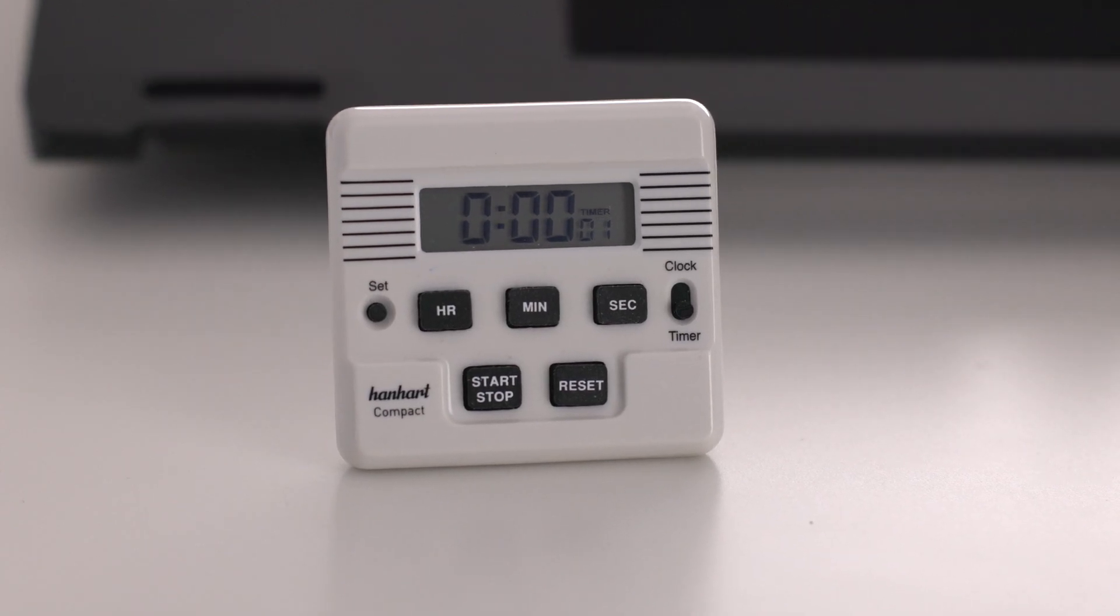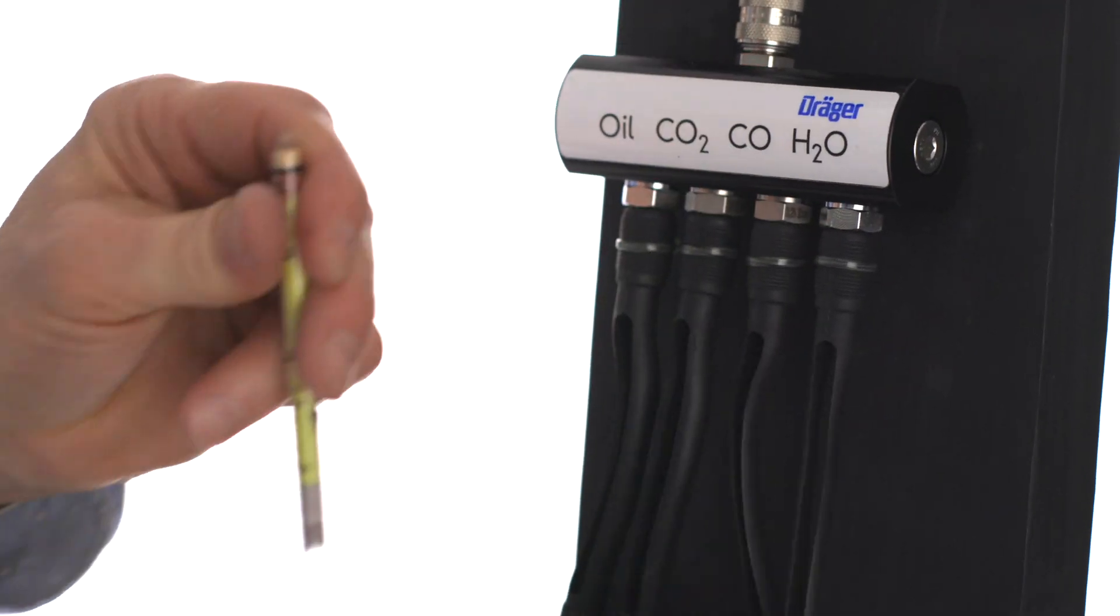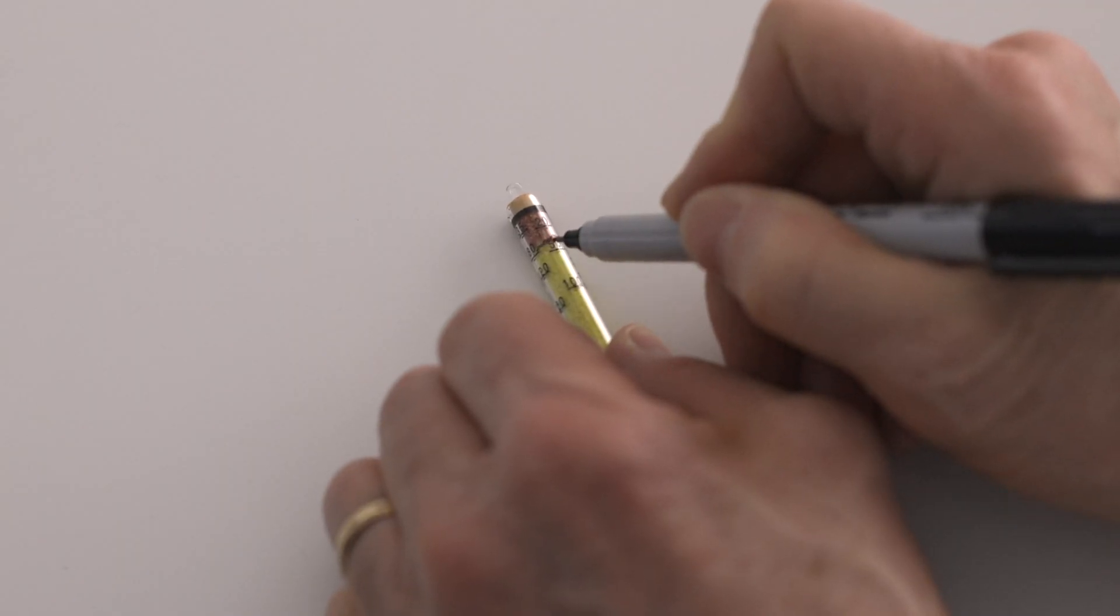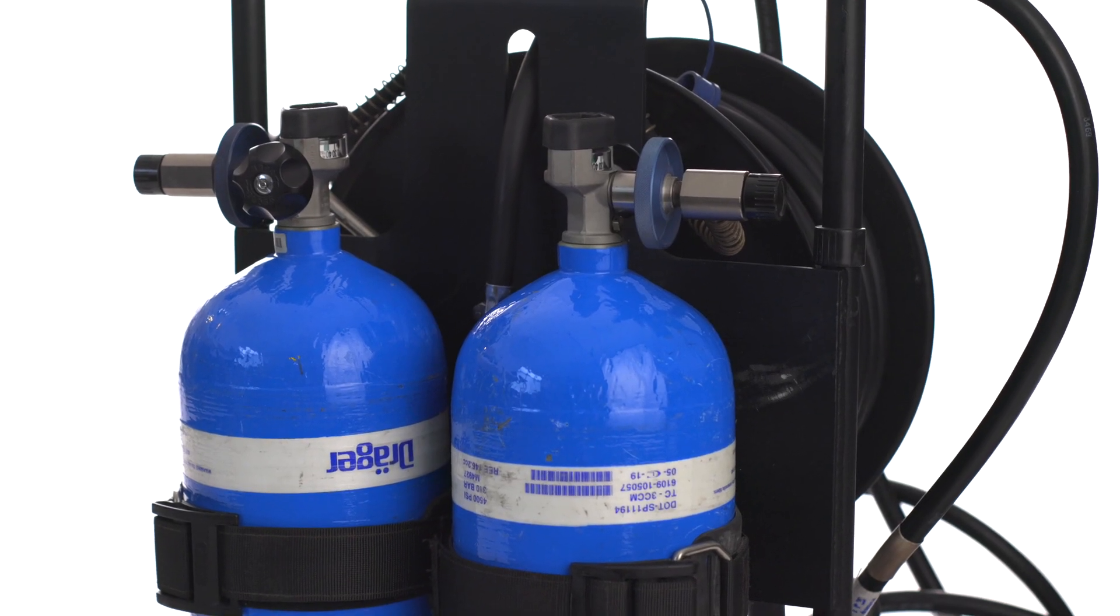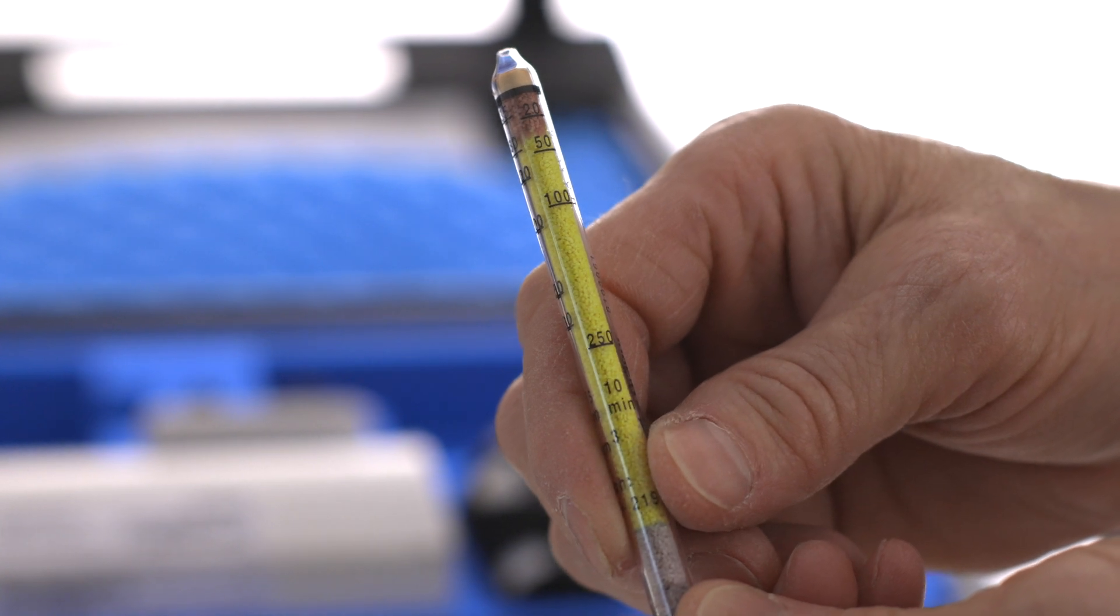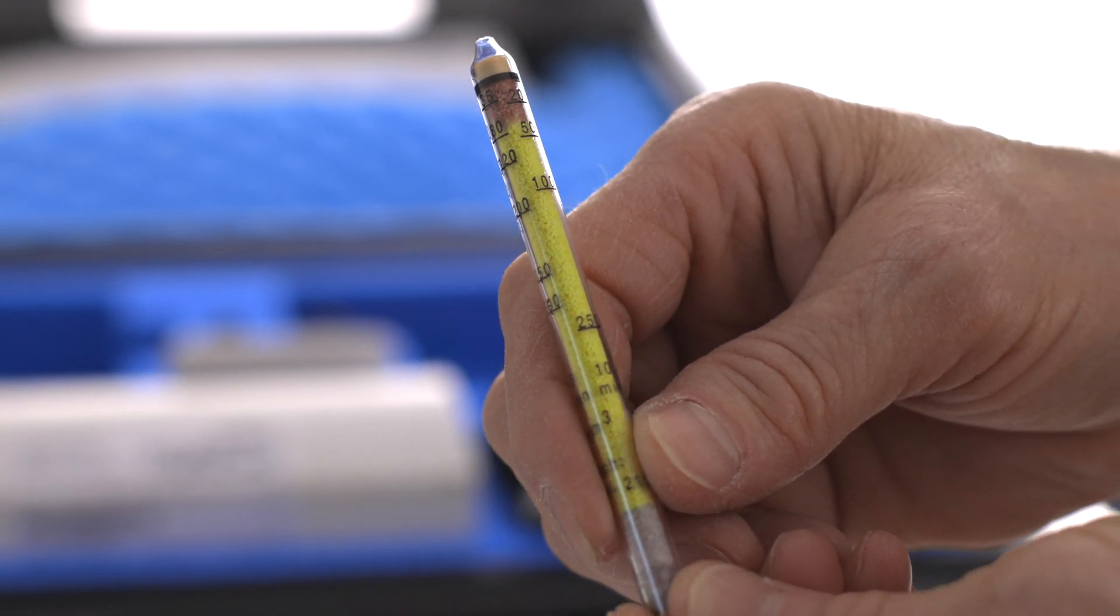When the second alarm goes off, remove the water vapor tube and immediately evaluate the reddish-brown discoloration on the tube. Compressed breathing air requires the use of a 10-minute test with acceptable results between 20 and 250 mg of water per cubic meter. This tube shows a discoloration of 35 mg of water per cubic meter.